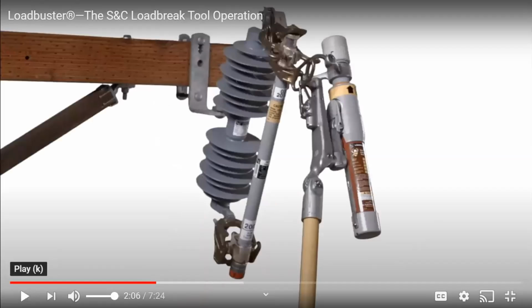Okay, so he's got actually a 34 kV, 600 amp nominal, 900 amp maximum tool. So obviously we know what voltage we can use it on. That's a weird fuse barrel configuration right there that you're looking at. What do they mean by 600 amp nominal, 900 amp maximum? Is that an up-to or an around kind of thing?